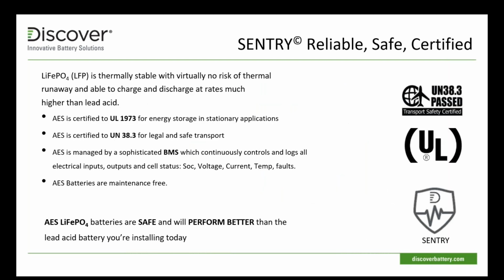The first of the features we call SENTRY, really gets to reliability, safety, and certification. So we've chosen the lithium ion chemistry for our battery. This is the safest, most stable of the lithium ion. This is the one that you really want out there. Its thermal stability is the best amongst the lot of lithium ion. We are certified to UL 1973, which is important. This is the stationary certification for a battery pack. It's not a cell rating, it's actual pack rating, which is important.